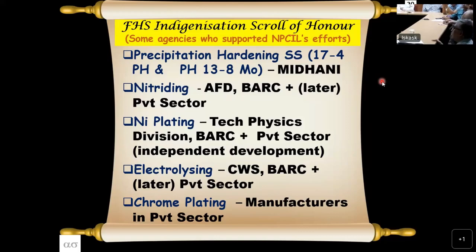Now, next comes nitriding. The problem with 17-4 PH, the problem with the fueling machine head, is that it has to work in water, which means corrosion resistance is required. It means stainless steel is required. Stainless steel cannot be hardened very much like a carbon steel. So the surface has to be hardened in some way, treated. Also a wear pair, 17-4 PH versus 17-4 PH, is very bad. It will seize. So if you have two parts of 17-4 PH running one on the other, one of them has to be surface treated somehow. There are several methods, and out of that, nitriding is one.